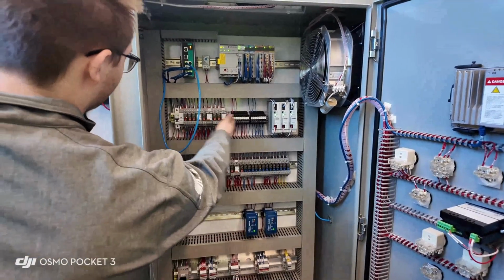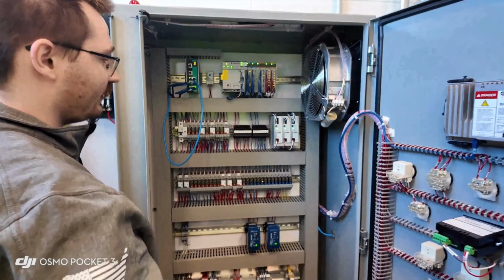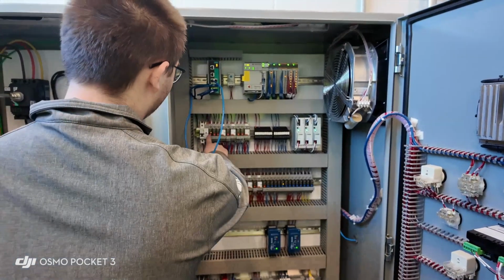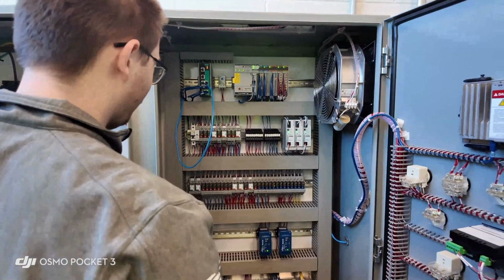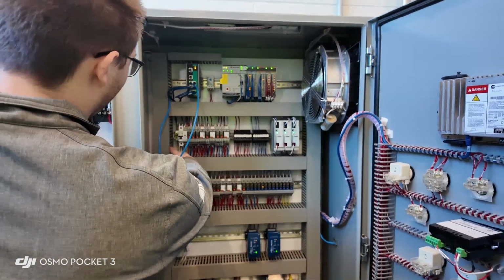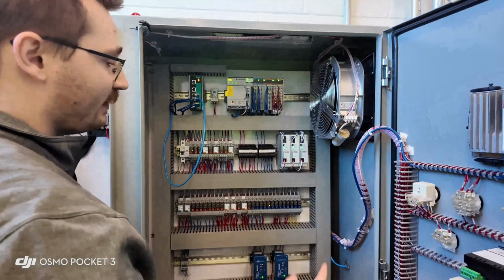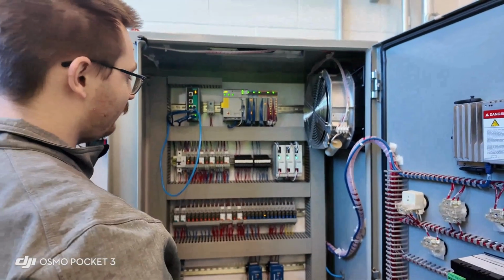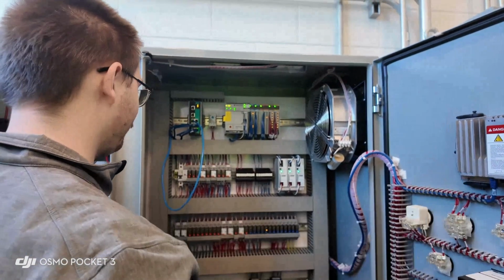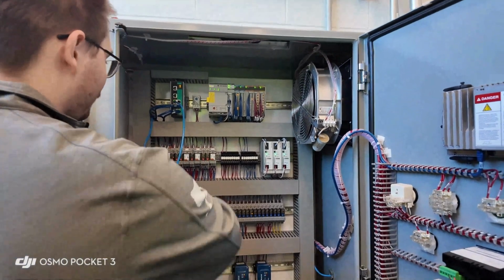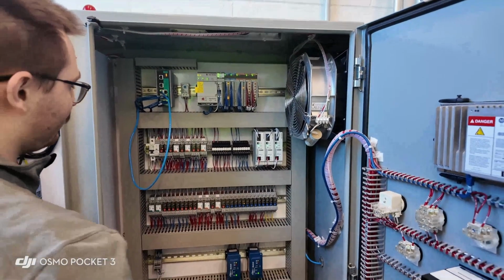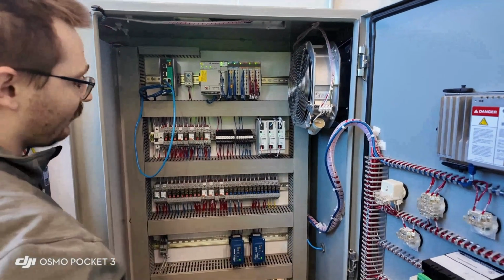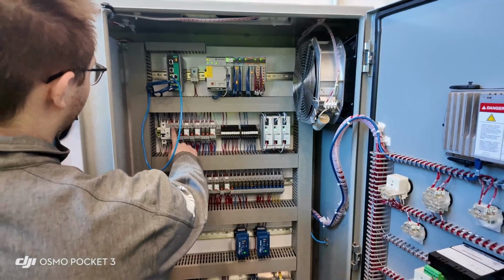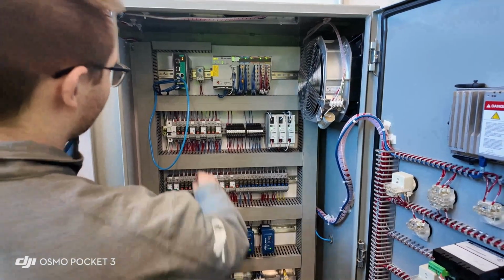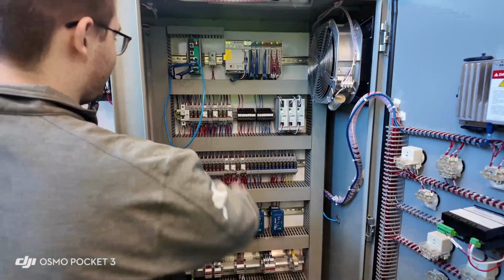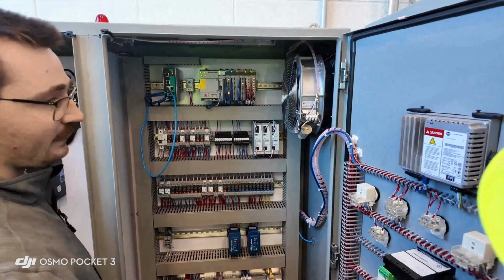So this leads us to some of the relays that are taking in signals from the wet well and the power. The first one's your power fail relay, like I was talking about with the UPS. If you lose control power, this is going to swap over, and the UPS is going to take on control voltage for a little while, and it's going to alert you. Ringing alarms, these are just alarm circuits. So we have our alarm relay and our silence relay. If there's any alarm, it's going to activate your alarm relay, and then you can use the silence relay to silence the horn.